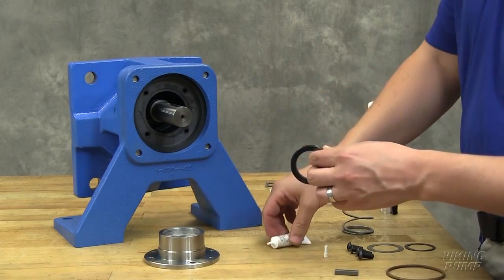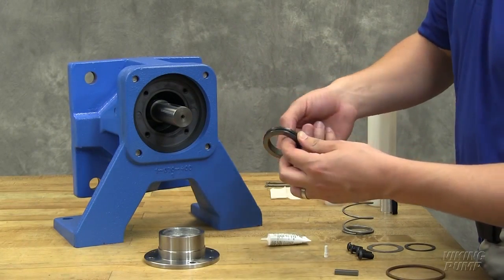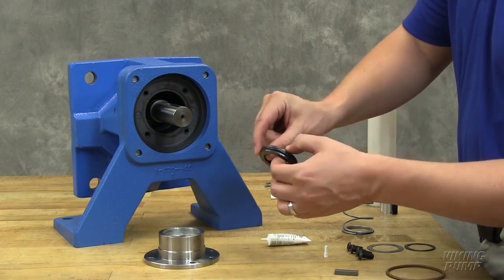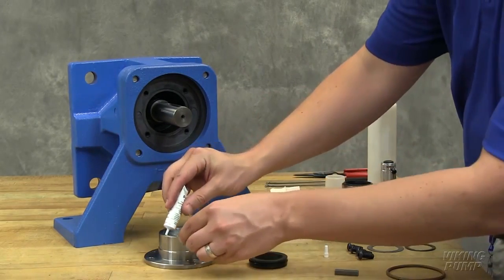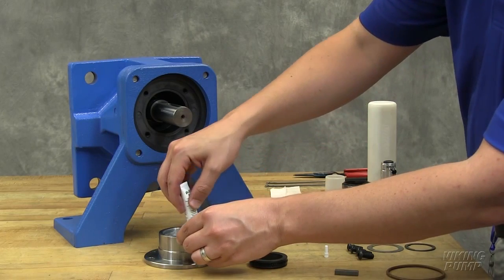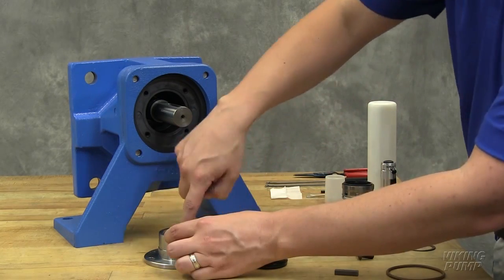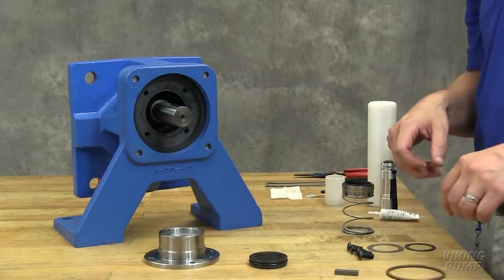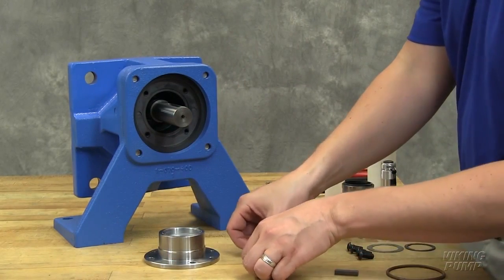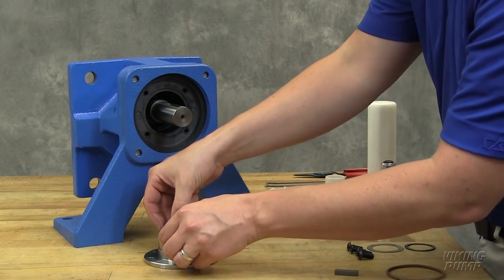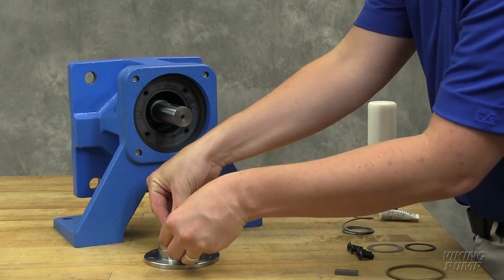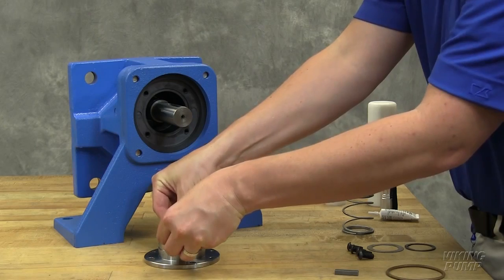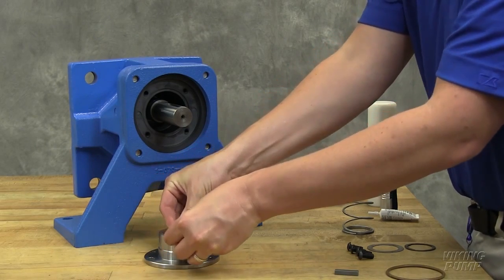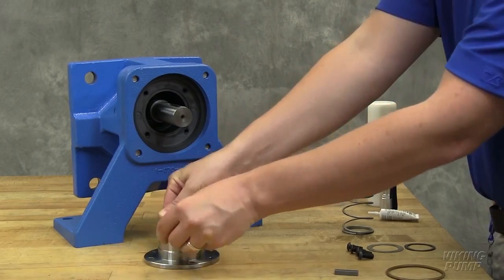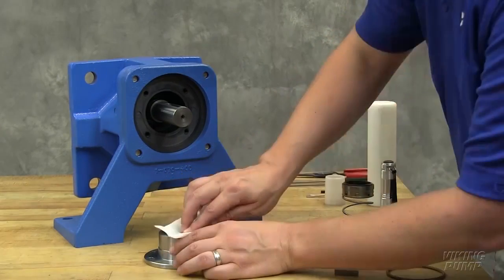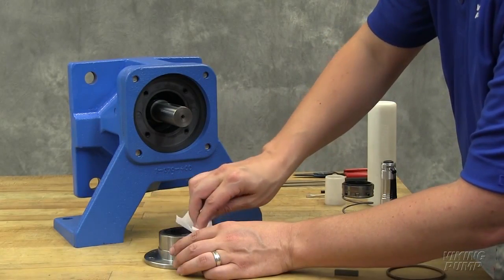To install the new silicon carbide stationary seat, first lubricate the O-ring on the stationary seat with a generous amount of light oil. Also lubricate the bore for the stationary seat. Second, use your thumbs or the heel of your hand to press the stationary seat into the bore of the seal holder. Remember, the face of the stationary seat has been lapped to a mirror finish. Any damage done to this face during installation will affect the ability of the mechanical seal to seal. Wipe the seal face clean with a lint-free towel.